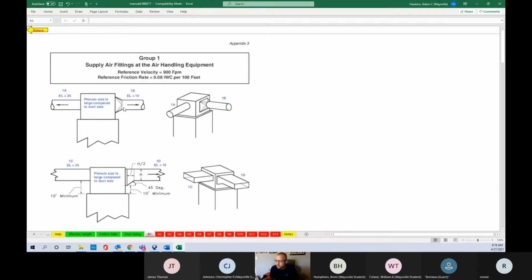Or I can put this little transition that's on this right side on this 1B fitting, a little more work. But if I'm trying to save length, it may be worth it to actually transition this. So anytime you can make the air work its way in versus just abruptly having to force its way through, it reduces your equivalent length quite a bit.